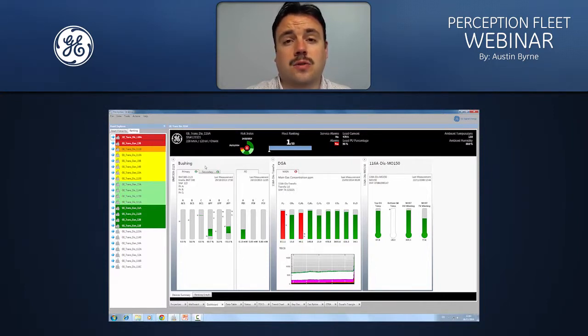This asset is the worst asset of a fleet of 23. It has no service alarms, but it does have a concentration alarm. You can see its current load and its load PU percentage, and you can also see the ambient environment information for this asset also.